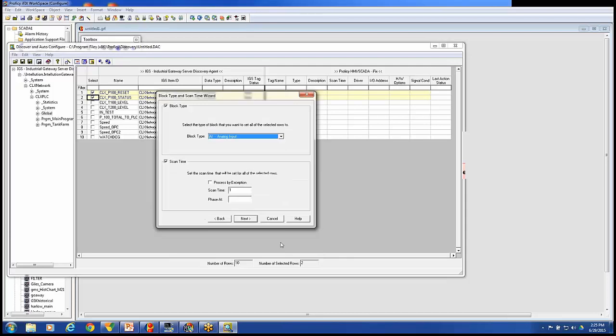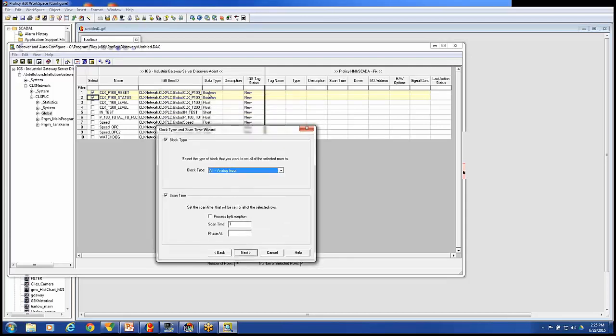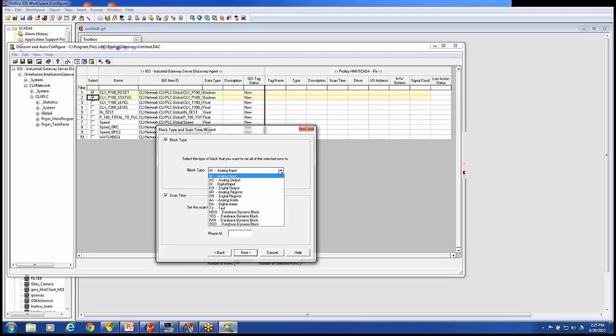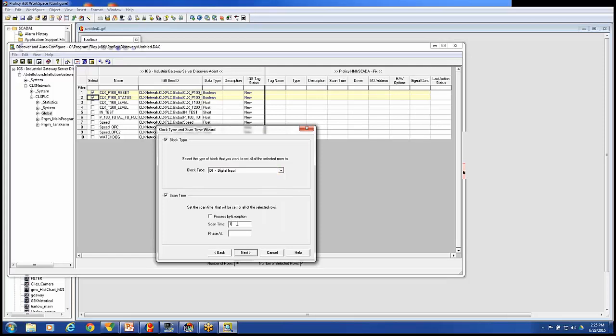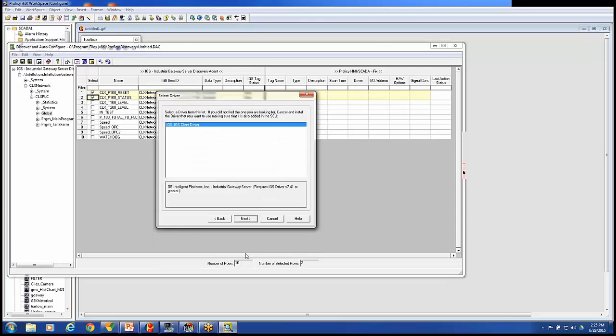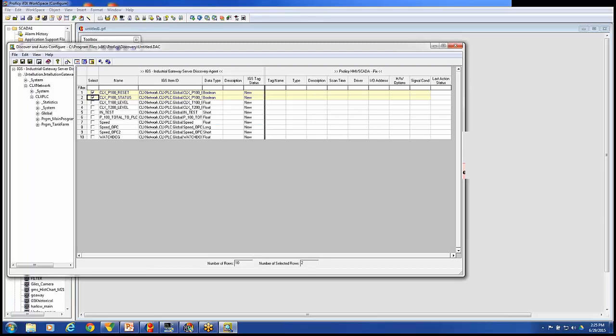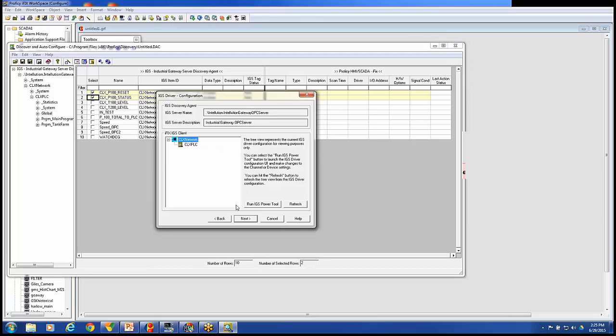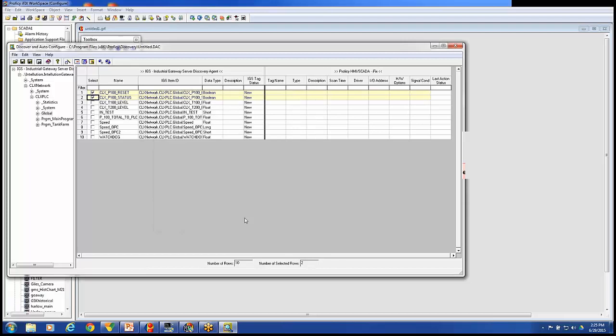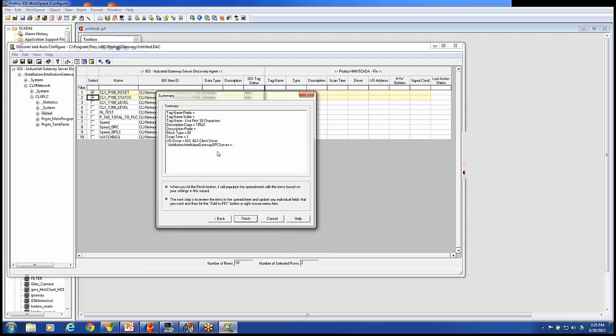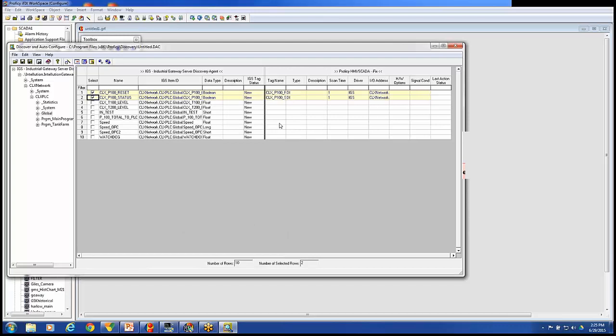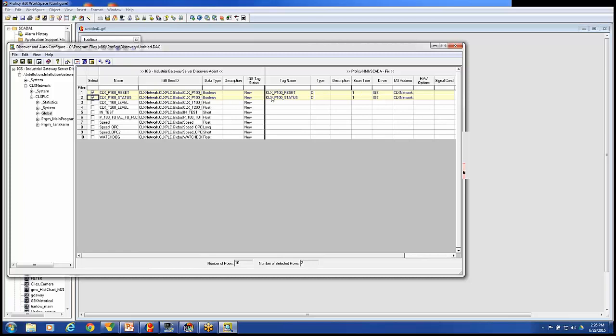We'll hit Next here. I did select two boolean tags. So I will choose that those are going to be digital input tags. And I'm going to process them at one second scan time. Hit Next. We are going to use the IGS driver. This tells me what PLC it's going to connect to. And finally what it's going to do. We hit Finish. And we see that this is how it's going to prepare it. It's going to bring over a tag CLX P100 reset, CLX P100 status. Here's the IO address that it's using for those devices.